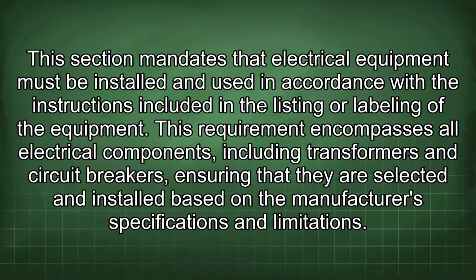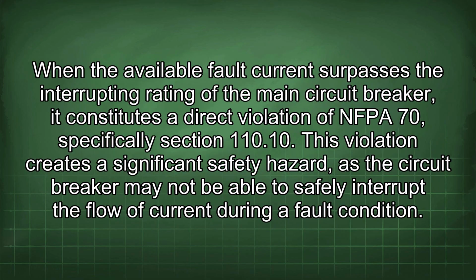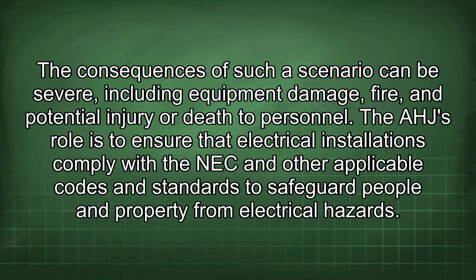This requirement encompasses all electrical components, including transformers and circuit breakers, ensuring that they are selected and installed based on the manufacturer's specifications and limitations. When the available fault current surpasses the interrupting rating of the main circuit breaker, it constitutes a direct violation of NFPA 70, specifically Section 110.10. This violation creates a significant safety hazard, as the circuit breaker may not be able to safely interrupt the flow of current during a fault condition. The consequences of such a scenario can be severe, including equipment damage, fire, and potential injury or death to personnel.